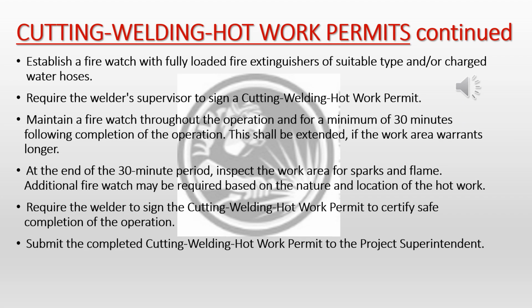Cutting, welding, hot work permits continued. Establish a fire watch with fully loaded fire extinguishers of suitable type and/or charged water hoses. Require the welder's supervisor to sign a cutting, welding, hot work permit. Maintain a fire watch throughout the operation for a minimum of 30 minutes following completion of the operation. This shall be extended if the work area warrants longer.